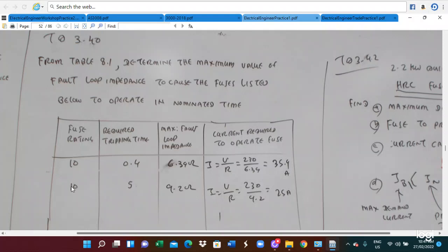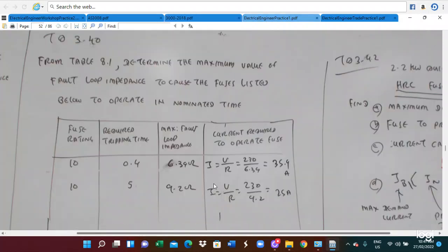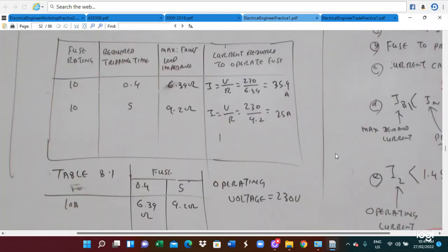For the 10A protective device with a 5-second tripping time, the maximum loop impedance from Table 8.1 is 9.2Ω. So 230V divided by 9.2Ω gives us 25A. This is the way we calculate the operating current from the loop impedance values.